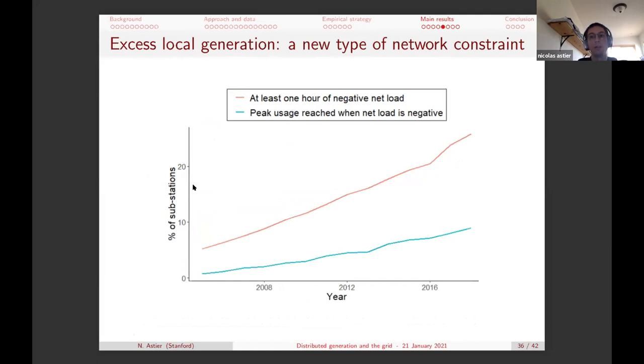And if this phenomenon amplifies, at some point, this reverse power flow starts to be actually higher in absolute value than the peak flow you historically had in the other direction. And so it starts being a concern in terms of how much capacity you need for the distribution grid, because you want to make sure the distribution grid is able to deal with these very high local generation hours. And so the substations where you observe this kind of phenomenon historically, so the substations for which the peak usage in absolute value was reached during an hour where power was going from the distribution to the transmission grid, used to be very marginal.